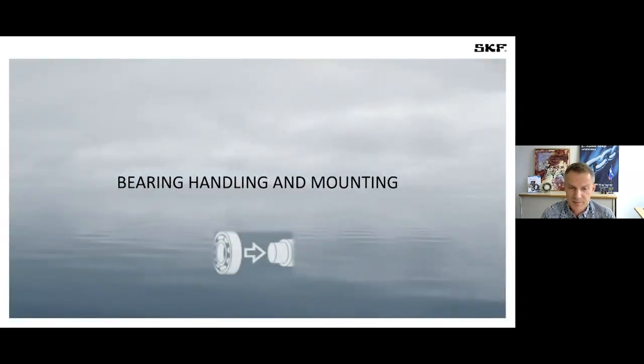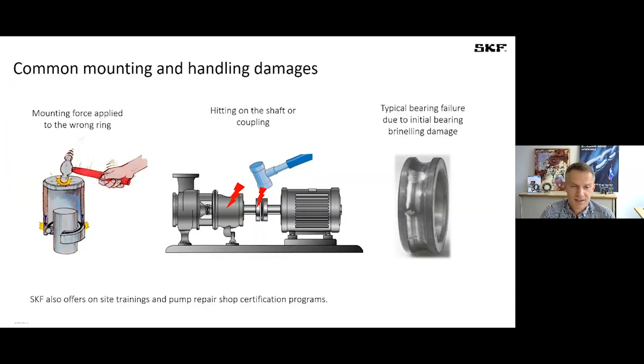Some words on bearing handling and mounting, very basic stuff but it still happens. I only want to point out the left one. It still happens that bearings are mounted on the shaft by pushing on the outer ring. So please don't push the bearing to the shaft via the outer ring. You have to push on the inner ring, which we will see in one of the next slides. Otherwise you might end up with damages like seen on the right side here.